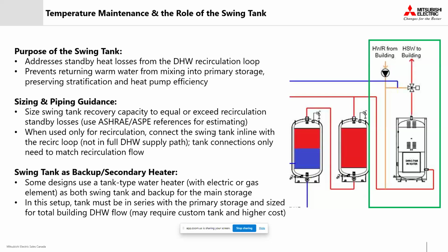That's where a swing tank or temperature maintenance heater comes in. Its primary role is to handle these standby losses by reheating the return circulation water without mixing in the main storage tank. This is going to preserve our thermal stratification, keep our main storage hot, and boost our overall system efficiency.